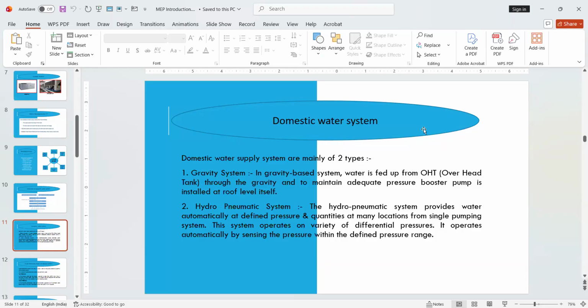It operates automatically by sensing the pressure within the defined pressure range. For example, our building is of 40 floors, so there will be a hydropneumatic pump installed in the pump room. From that hydropneumatic pump, we will give connection to all the toilets and all the flats. There will be a pressure which we will define for that particular pump. The pressure can be 7 bar, 8 bar, whatever pressure we define. So all the lines will be charged with 7 bar.